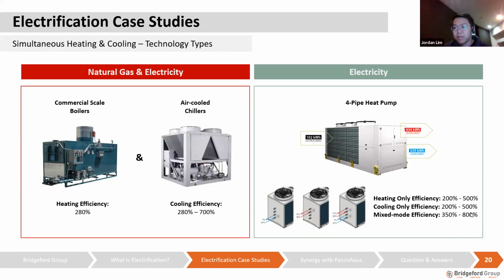But then again, this is the information that I got from a year ago, and every year you have more efficient systems coming out. So I wouldn't be surprised at all if the overall efficiency that can be achieved by a 4-pipe heat pump can go all the way up to 10.0. Right. So efficiency for running heating only and cooling only is not as great, right? So that's probably something to take note of.